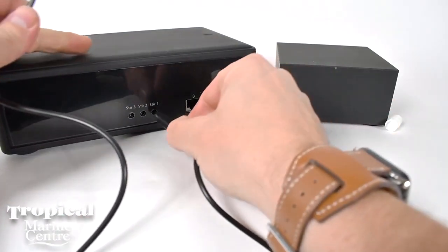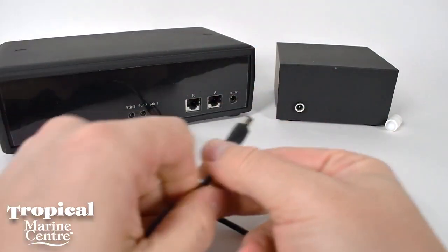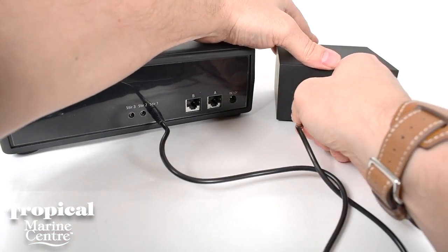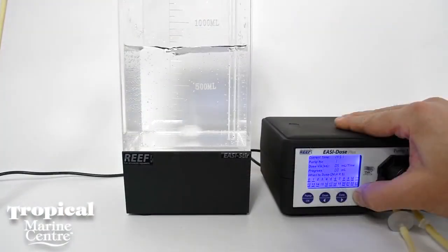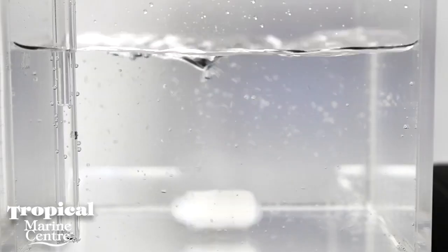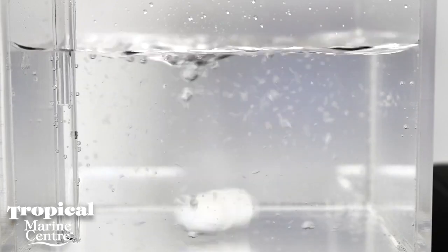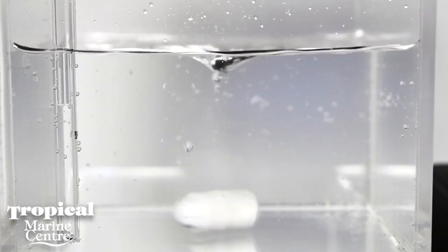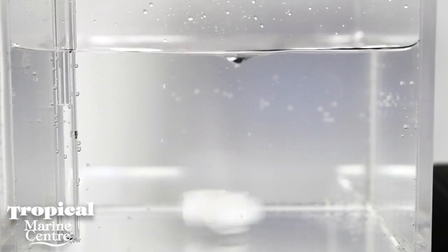The little end goes into the doser, whilst the big end goes into the Easi Stir unit. With everything connected, if you press the manual feed button, it will whiz up the stirrer. This will mix your liquid. It will also dose at the same time. When in normal operation, the doser will mix your liquid 30 seconds before it doses.